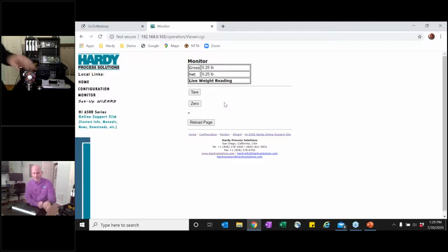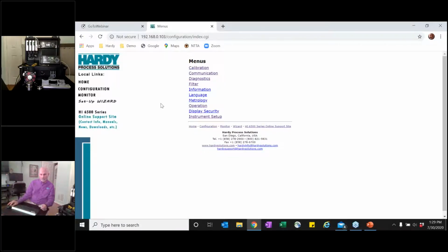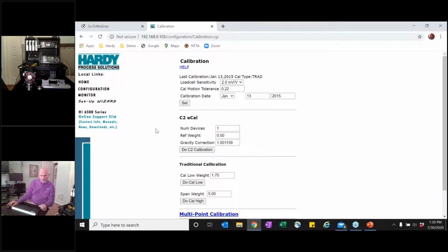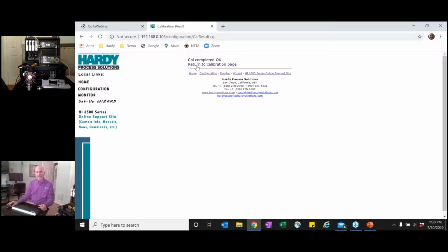So let's do the smart calibration. And for the smart calibration, we're going to do that here on our front panel. And we go right into this calibration. And we just pick this C2 calibration right here. And it says there's a reference weight of 0. And we want to tell it, do a C2 calibration. It says it's complete, that it's been completed.